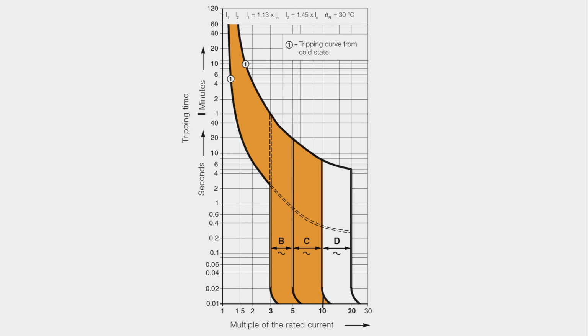Right, so let's have a look at a circuit breaker. Now, circuit breakers have something called tripping curves, and we get different types of curves, B, C, D. There's actually quite a few, but these are the common ones. Now, what we see here is the multiple of the rated current. So say I want to protect it for 80 amps, that would be the maximum, so that would be 80. Then this would be 160, so it's 2 times the current that I'm referring to. So if I want to go even higher, this is 3 times the rated current.